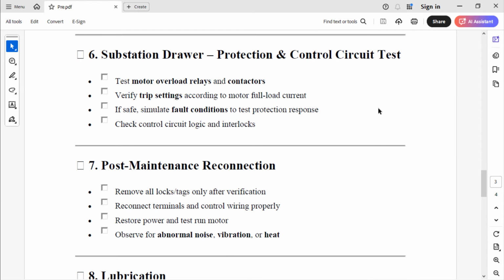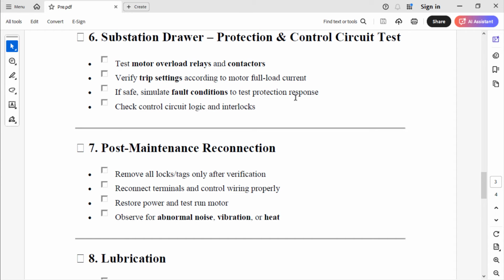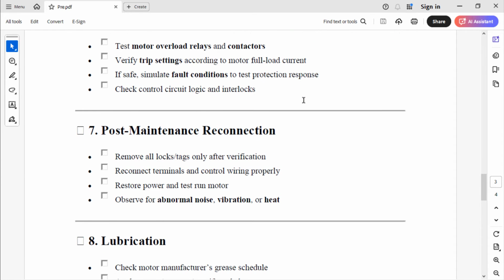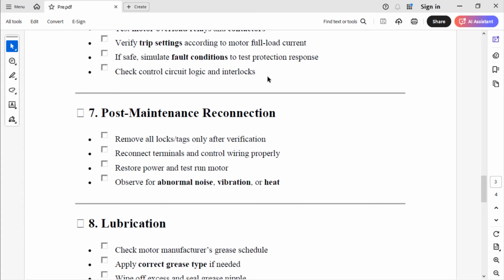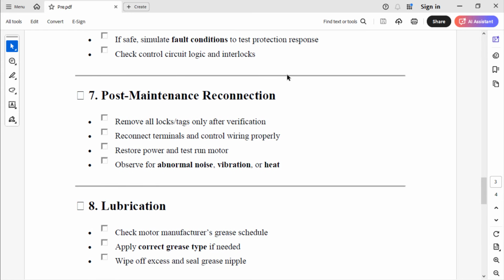Let's now go to the substation drawer and see the protection and control circuit. Now, first of all, let's retighten anything that needs retightening. After that, let's test motor overload relays and contactors, if applicable. Also verify trip settings according to motor full load current. If safe, simulate fault conditions to test protection response. Check control circuit logic and interlocks.